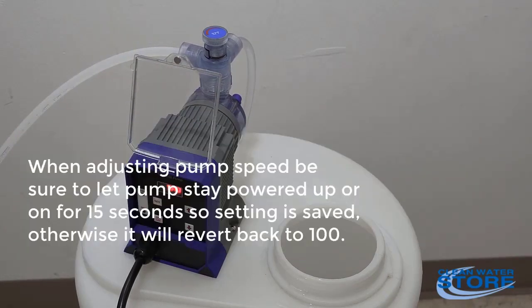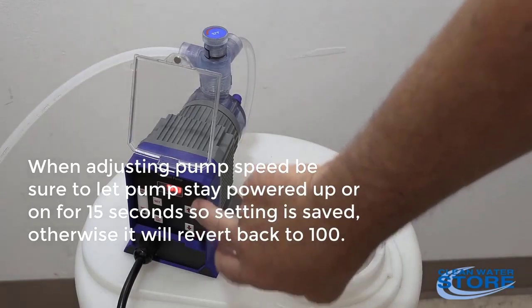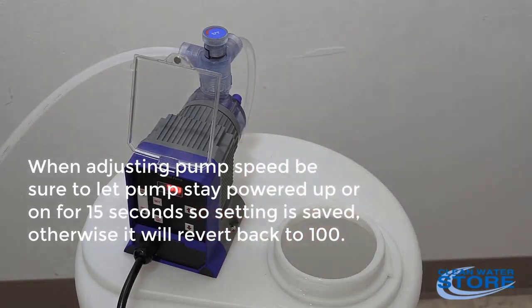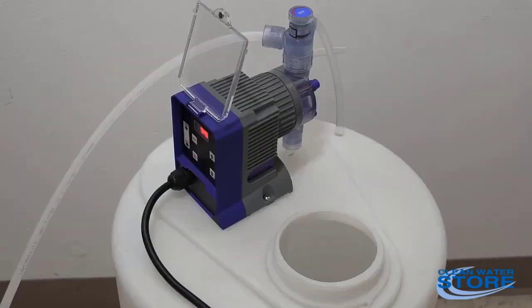A couple other things I wanted to note. First of all, if you do adjust the speed here, once you adjust it, wait 15-20 seconds for it to set. It won't hold it into memory if you don't. If you unplug it or shut the power off now, it would go back to 100% if you don't wait that 15 seconds. Alright, thanks folks.